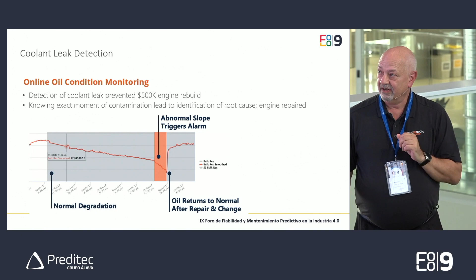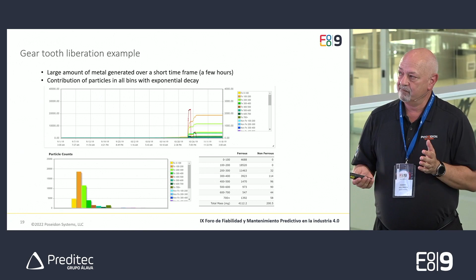And let me quickly get to the metallic debris sensor. The analog signal, this is what one particle looks like traveling through the sensor. This is a wind turbine gearbox. The different colors are total counts observed of certain particle size. Excuse me, here's a table of the counts in those different bin sizes. You see a histogram. What I'm trying to show here is when this gear tooth fracture occurred, there was a large burst of metal with really no warning ahead of time. Using periodic sampling wouldn't have identified that. That signature looks drastically different from a bearing spall.